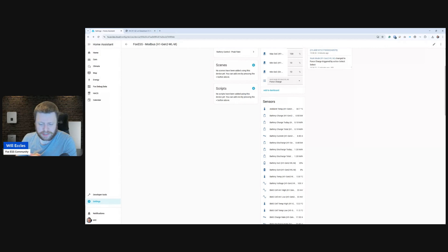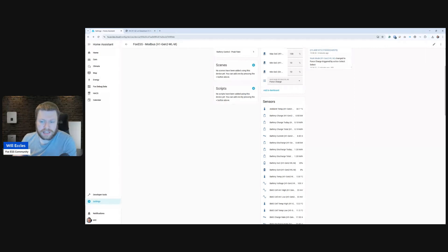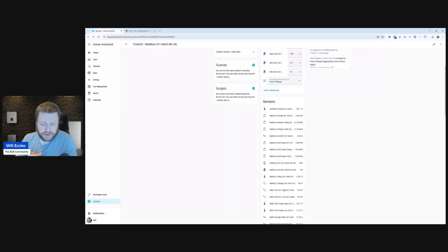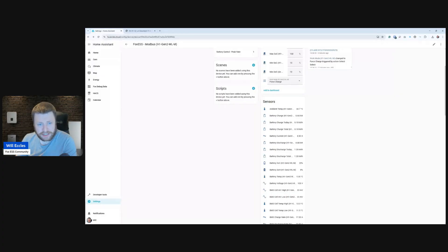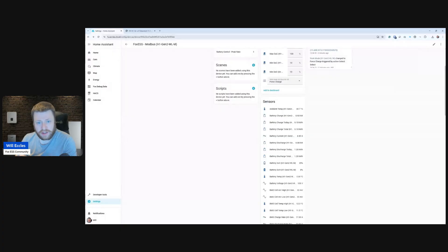And I thought that's a bit strange because the wireless dongle on all the previous versions has never exposed access to the Modbus server. So it looks like the very latest generation on the latest firmware of Fox inverters is actually supporting a Modbus server access through the wireless dongle.